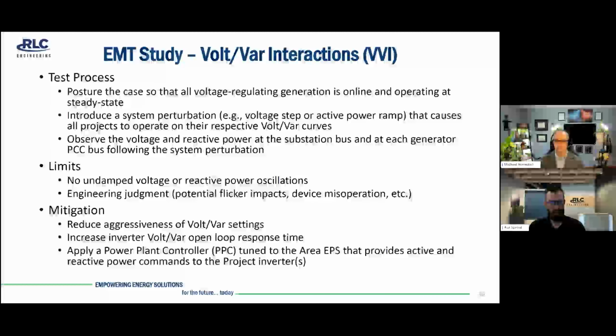Our last technical topic here, volt-var interaction assessment, or VVI. So this testing involves posturing the case such that DERs operate at a steady state within their voltage profiles. Then we apply some classic control theory and perform a step change that causes all projects to operate on their volt-var curves. And then we repeat the same exercise with a ramp change, and then observe the voltage and reactive power characteristics. So the limits here, one, ensure no oscillations or voltage hunting, essentially adverse control interactions between projects operating the volt-var.